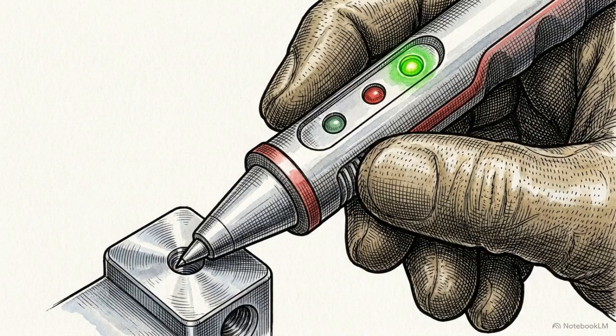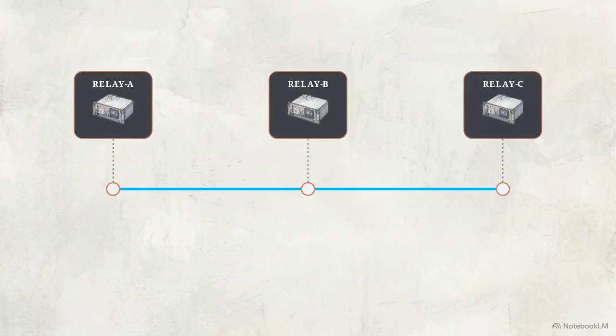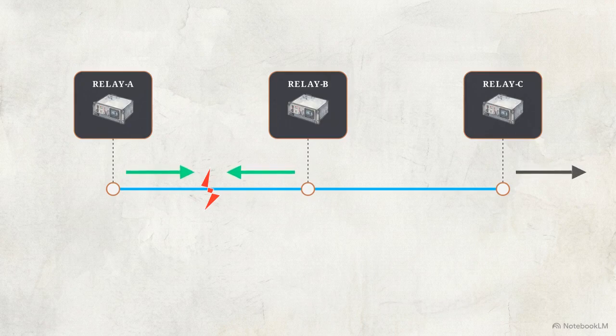An operator tests the secondary terminals using a handheld polarity probe. A green LED confirms the signal is perfectly aligned. A red LED immediately flags a reversed or distorted response. Polarity alignment acts as the geographic compass for the power grid. It ensures that protection relays detect faults in the correct direction rather than mistakenly tripping offline during healthy circuit operations.